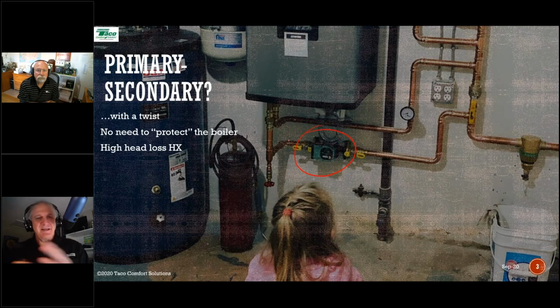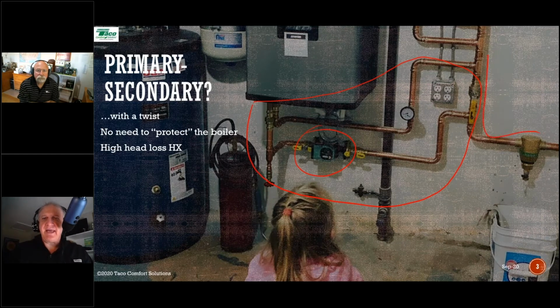Now, most people will refer to this setup, this piping right here, the boiler piping, as the primary, and then the header, the distribution header, as the secondary. And if you're comfortable with that, that's cool. I always call the big pipe the primary and the smaller pipe the secondary, but that's just me. So as long as you understand what it is, understand your terminology, you're fine.